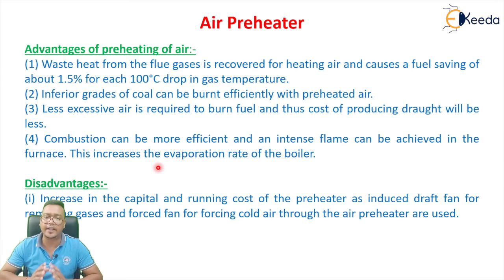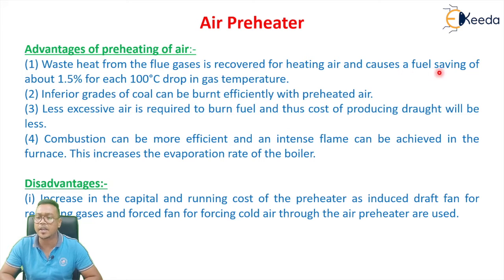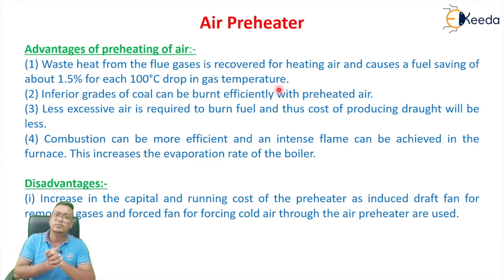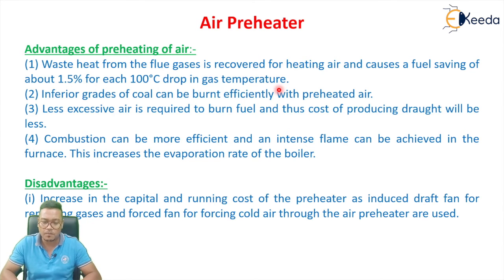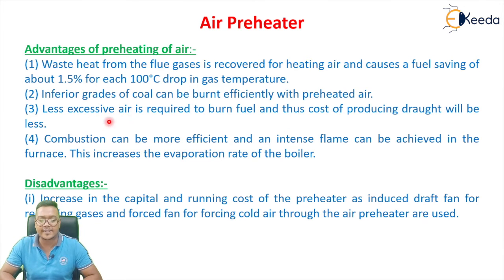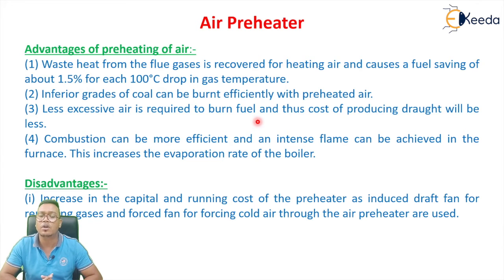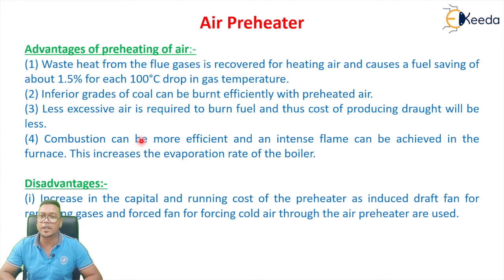What are the advantages of the air preheater? The waste heat from the flue gas is recovered for heating air and causes a fuel saving of about 1.5% for each 100-degree drop in gas temperature. If we are preheating the air, we are saving fuel. Inferior grades of coal can be used for combustion, less excess air is required to burn fuel, and combustion can be more efficient — achieving a more intense flame in the furnace.